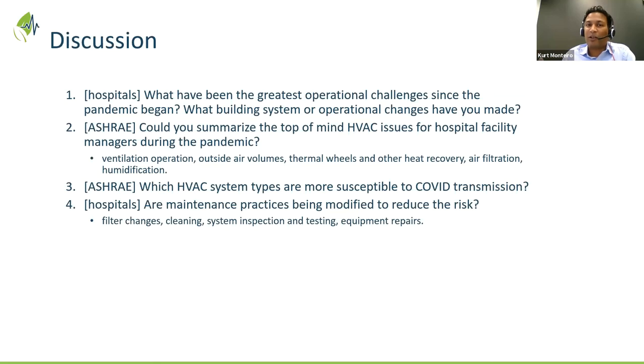If you've got enthalpy recovery wheels, they're already designed for low cross-contamination—typically configured so they don't cross-contaminate, so you've got less than 1% of that potential cross-contamination taking place. Even if there was cross-contamination across the wheel, it would be further diluted with all the outdoor air being brought in and distributed to a whole bunch of different spaces.